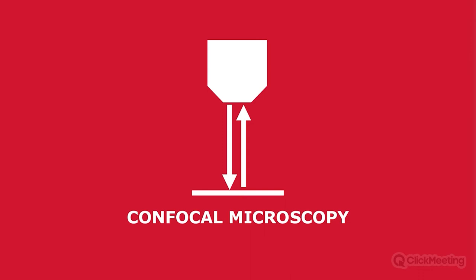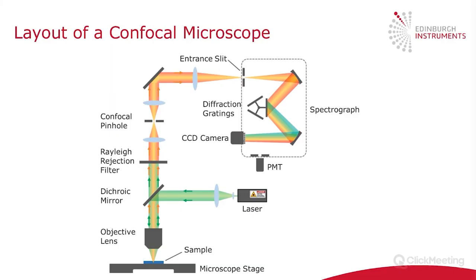So what is confocal microscopy? Here is a simplified layout of how a confocal microscope works for both photoluminescence and Raman. Starting with the excitation source, which is nearly always a laser. The laser comes in, it's reflected off a dichroic mirror and down towards the objective lens. This focuses the beam onto the sample to a point that excites the sample at that point. The sample is placed on a microscope stage, which is nearly always motorized, allowing you to move the point where the laser hits the surface.